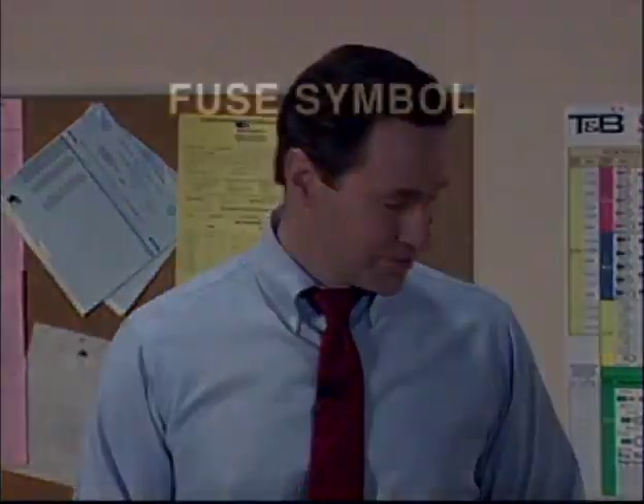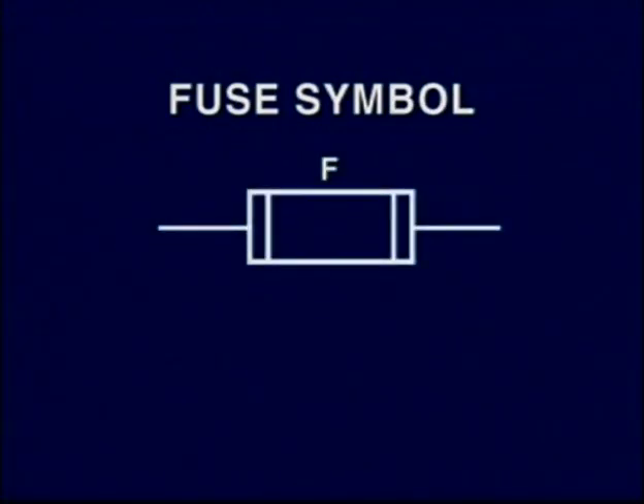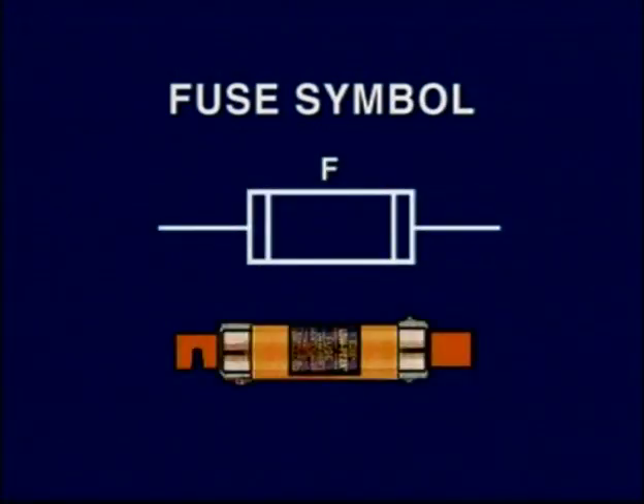This high current, if not cut off in a matter of a few thousandths of a second, will cause damage and destruction where severe insulation damage can occur. Additionally, it can cause melting of metal and conductors, vaporization of metal, ionization of gases and arcing, all of which can result in a fire. Fuses are used to reliably protect a circuit in which a short-circuit fault can occur. This protection is supplied by the design built into the fuse, which quickly disconnects the power being provided to a system. Fuses are represented by this symbol, which is a close resemblance of its original look.